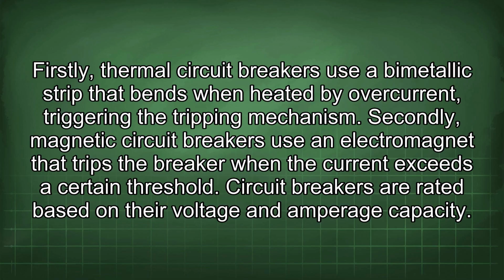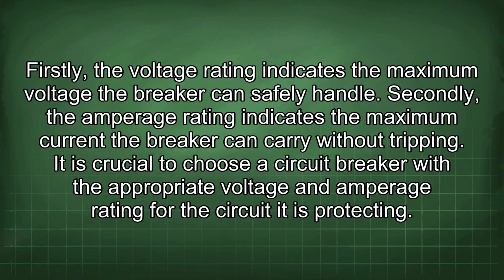Secondly, magnetic circuit breakers use an electromagnet that trips the breaker when the current exceeds a certain threshold. Circuit breakers are rated based on their voltage and amperage capacity. Firstly, the voltage rating indicates the maximum voltage the breaker can safely handle. Secondly, the amperage rating indicates the maximum current the breaker can carry without tripping.